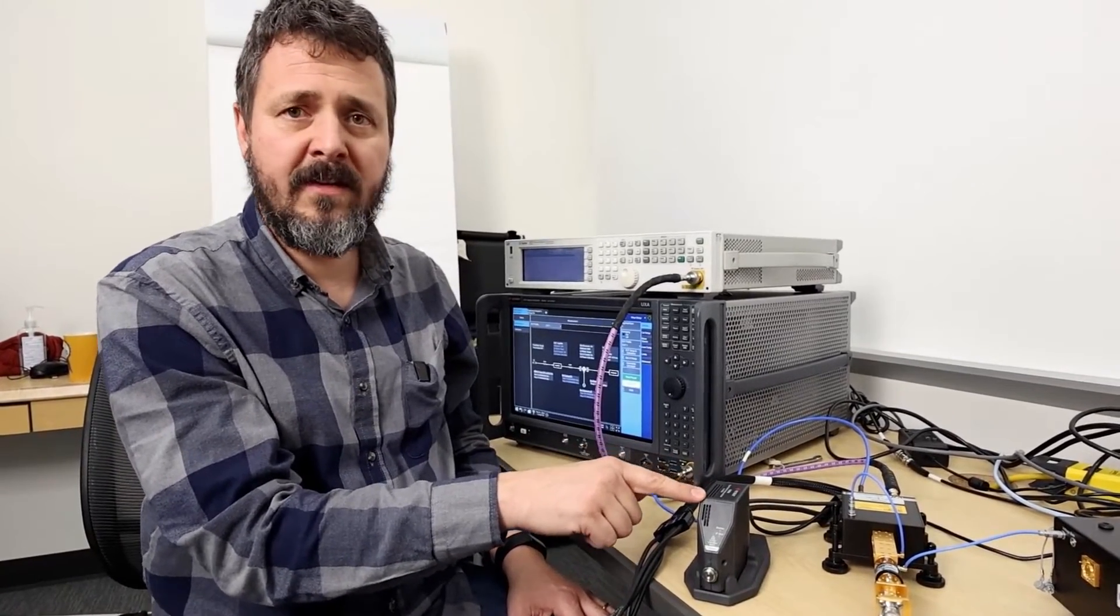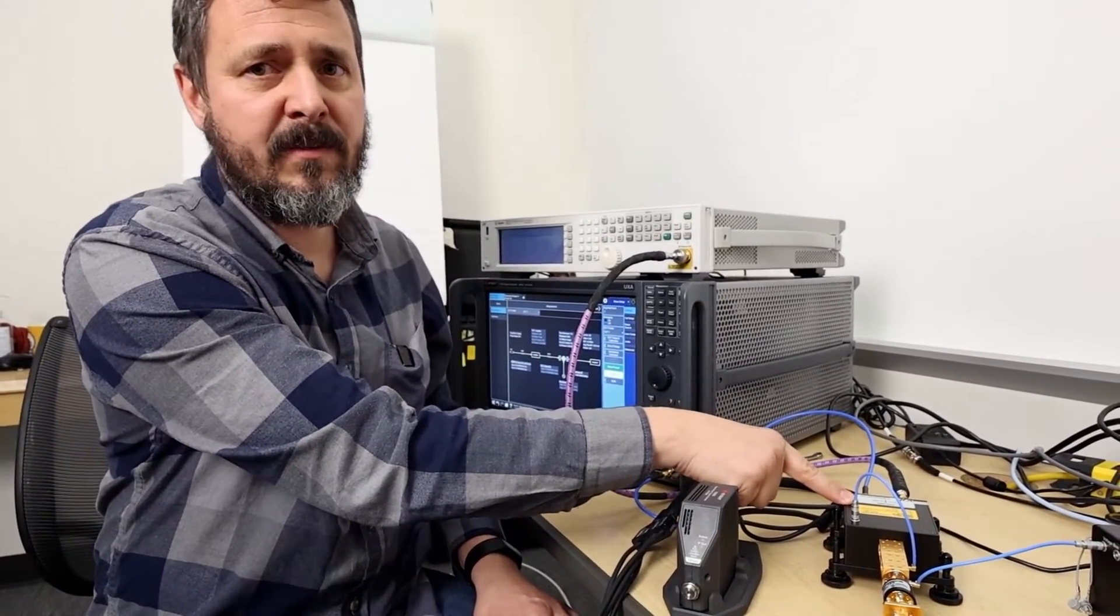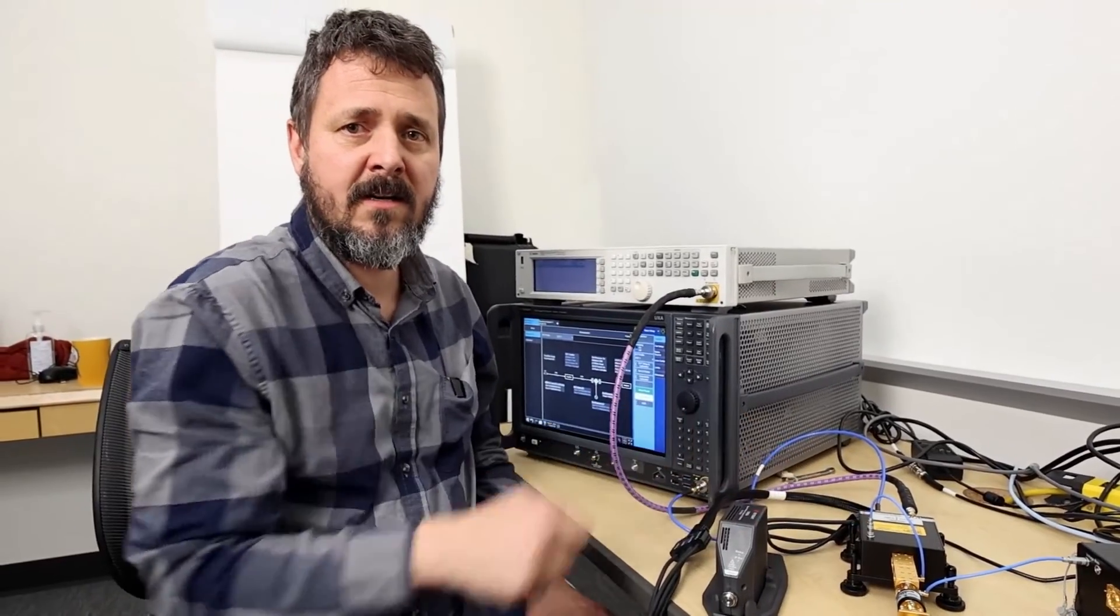So in summary, I've showed you two different ways to make noise figure measurements above 50 gigahertz. The frequency range extender works over 50 to 87 and a half gigahertz. With the VDI downconverters, you can make measurements all the way up to 330 gigahertz.